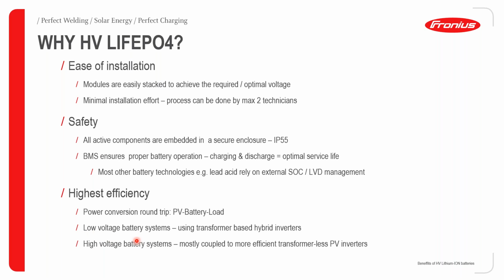Low voltage battery systems are mostly connected to transformer-based hybrid inverters. A transformer inside the inverter is not as efficient as a transformer-less inverter. The Gen 24 inverter from Fronius is transformer-less, and therefore you can achieve a very high efficiency of up to 98%. For very good hybrid inverters, when you're talking about conversion of DC power stored in the batteries to AC for application into the loads, we would have a best case scenario of about 94% or thereabout.